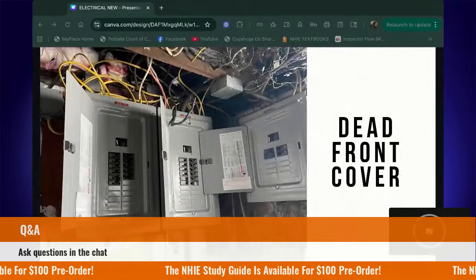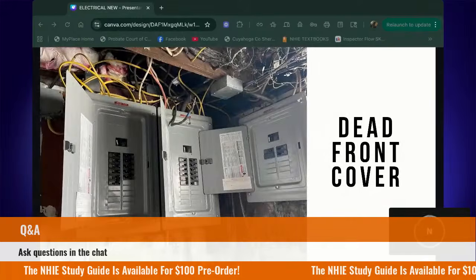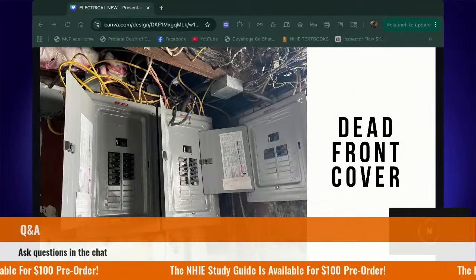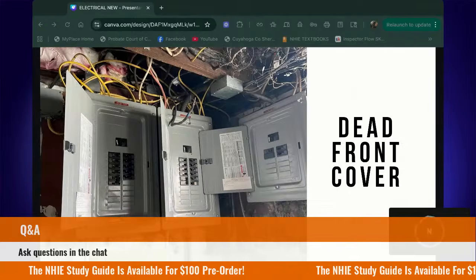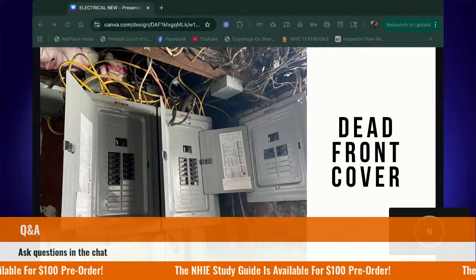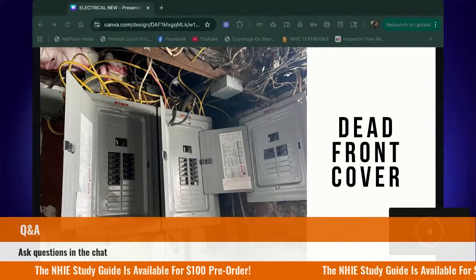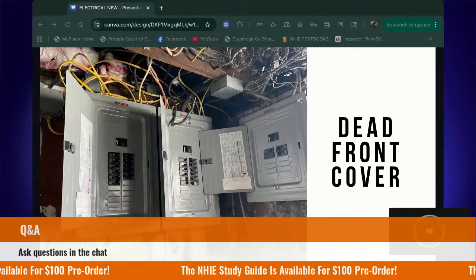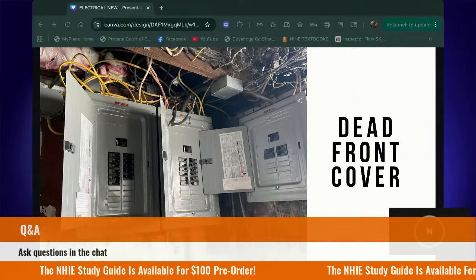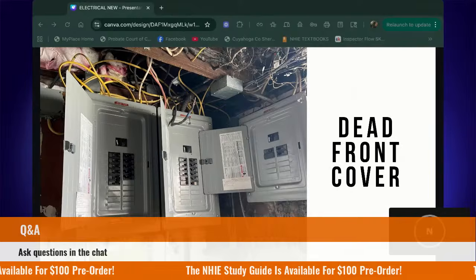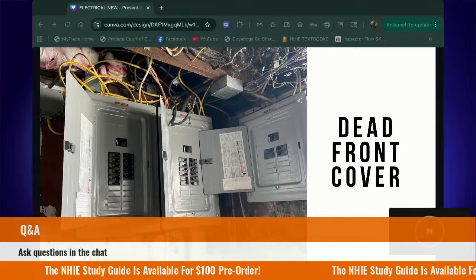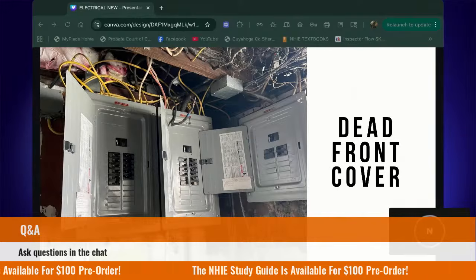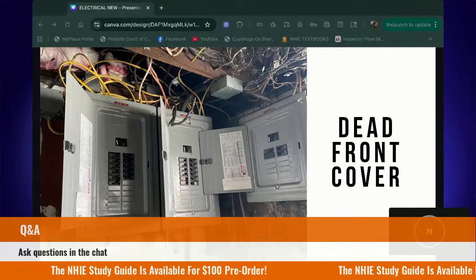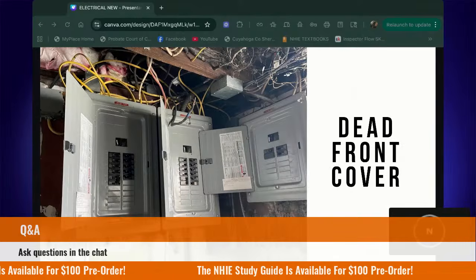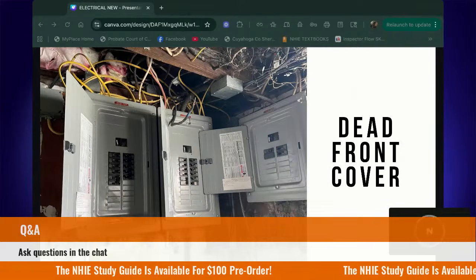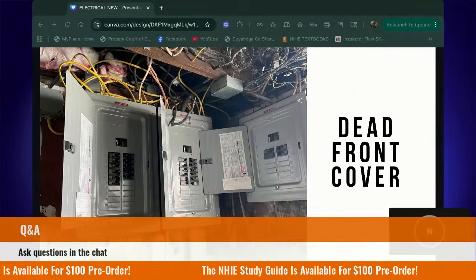And when we say open up the panel, we are talking about removing the dead front cover, which is just the front plate or the face plate of the actual panel. It is just keeping everything on the inside of the panel, again, the energized parts, safe. Okay. And when you remove the dead front, this is when you get to actually visually see what type of conductors or wires, the sizing. We can see what's going on with the neutrals and the grounds. We can see our lug connections. You can see if there's any evidence of overheating or burning, corrosion, rusting, all of that kind of stuff. So again, it is important that you remove it and that you are able to see it.